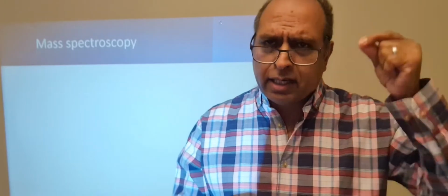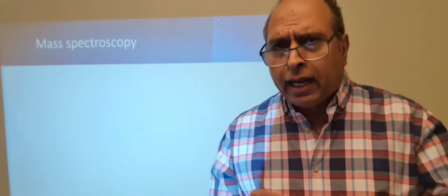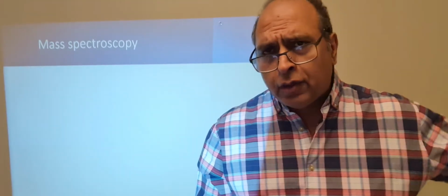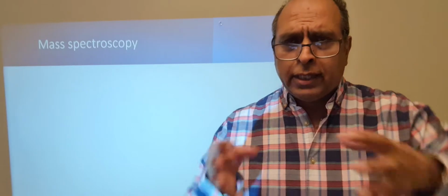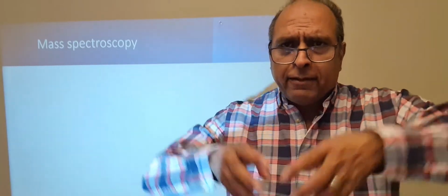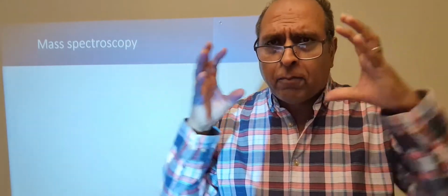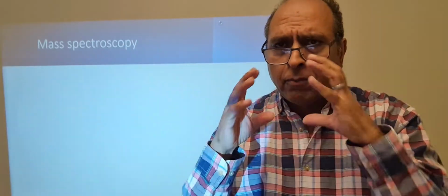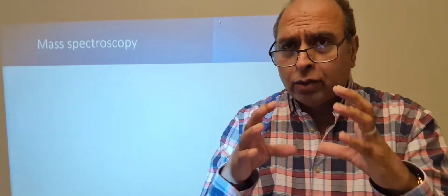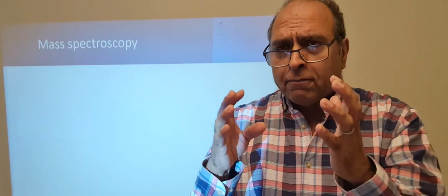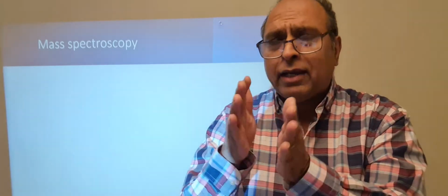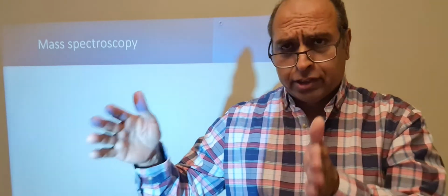The end of the needle is highly positively charged, and what that does is, if you've got the solvent and the unknown, what comes out is the unknown in droplets with the solvent, and as the solvent evaporates away, it will leave the molecule with a proton, the molecule with an H plus extra, and that molecule with an H plus extra will then undergo ion drift through a tube of a certain length.